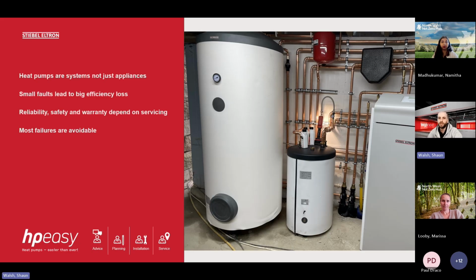With heat pumps, they typically don't fail in spectacular ways. What they generally do is drift in performance over time. And that's where the service and maintenance side of things comes in. When we go and do a service or a maintenance call, we are looking at how small faults can lead to big efficiency losses. We will cover some of the faults as well.